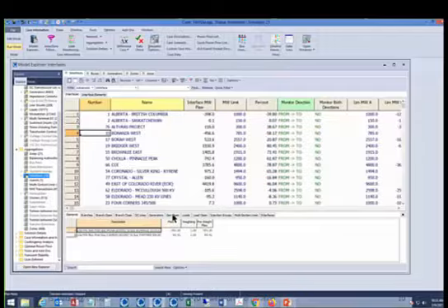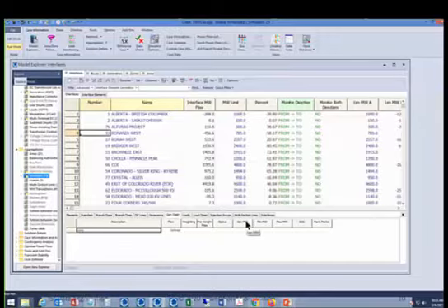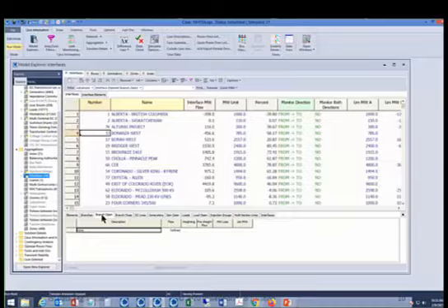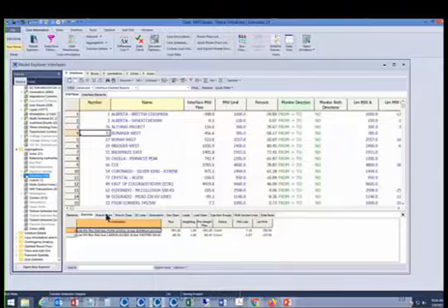It looks like we even have a generator open object, and I think that's for coming up with the impact of a contingency, like the loss of a generator. What would that do to the flow? So we have that for branches too, which is a little bit more common. You can have an interface that looks at the flow on one line if another line is taken out of service. Each of these tabs will give you a filtered list of the elements that are of that type.